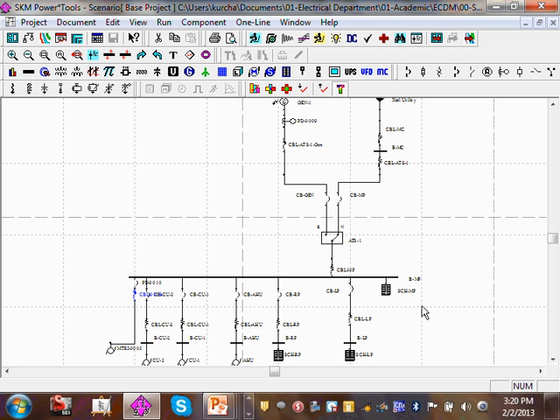Yeah. Well, what we do, guys, at least on engineer jobs, the owner wants an approximate price, right? That's what happens: they come to us as an engineer and say, what size cables, what size major equipment do you want? So we run our calculation for this hospital. We come up with a 4,000 amp switchgear and 85,000 amp interrupting rating main and a couple of MCCs here and there, and that's kind of the big picture. And typically, if you have done it before, you are off by 10 to 20%.